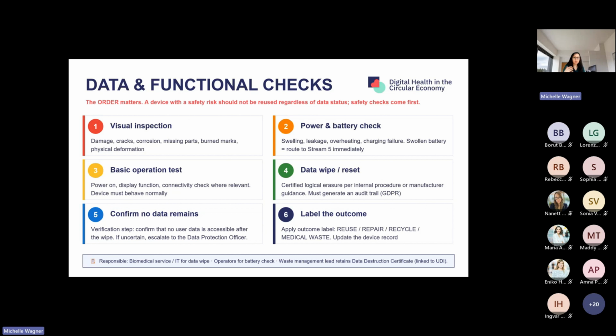You can think of, for example, a wearable cardiac monitor. Even after the patient has finished, the device may still contain relevant information like clinical measurements or timestamps, and it's very relevant. If that information isn't removed properly before the device leaves the hospital or the clinic, we no longer have just a waste management issue. We potentially have a data protection incident. That's why the sequence shown in the manual is so important: safety first, functionality, then securely erase data. Only once all of those checks have been successfully completed should a device be approved for refurbishment.